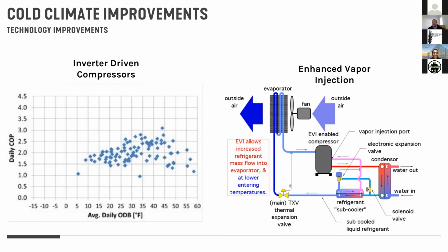On the right, though, is technology that's starting to infiltrate the market right now within the refrigeration market, and that is looking at what's called enhanced vapor injection. And I don't know if you can see my mouse, but the key thing is in the lower right-hand corner, just past the condenser heat exchanger, is an extra valve. There's an extra solenoid valve that's going to peel off a little bit of that refrigerant, run it past its own expansion valve, and steal additional heat off of the main refrigeration loop.